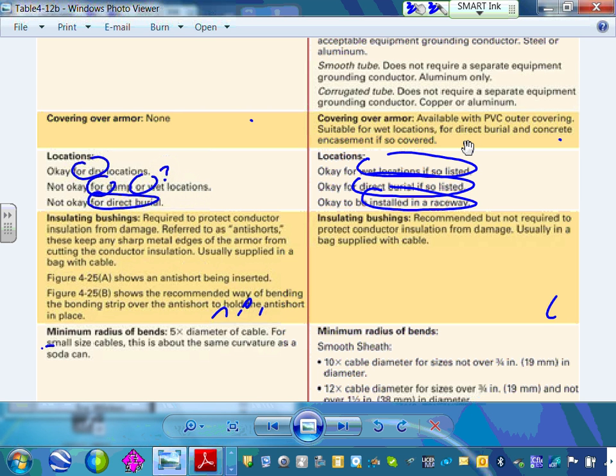Five times, look at all of them. Guys, this is for all cables. Can I get you to understand this is for all cables? Five times the diameter of the cable. So, Gary, what do you think the diameter of this cable is? Half an inch? Smaller than that? 3/8? Okay, 3/8. So you take the 3/8 and multiply it by 5.